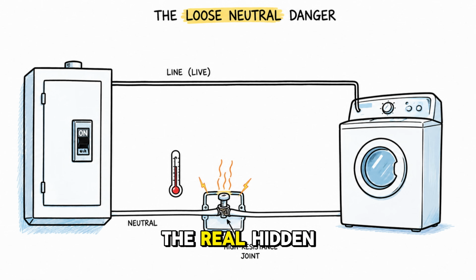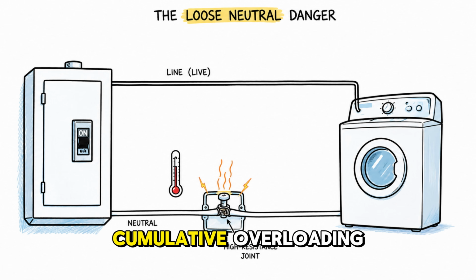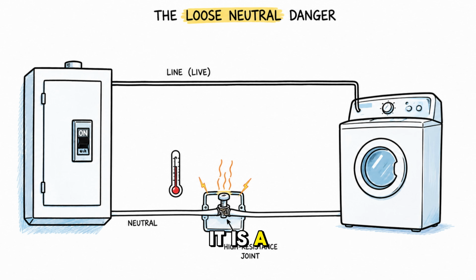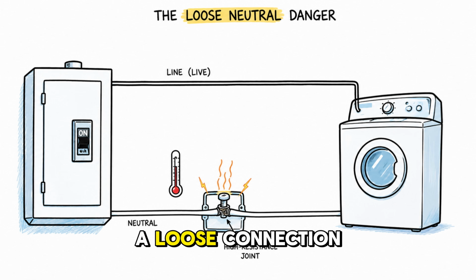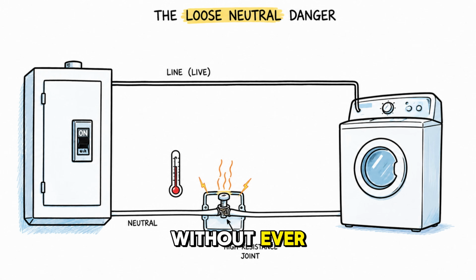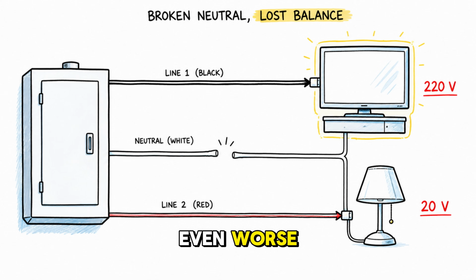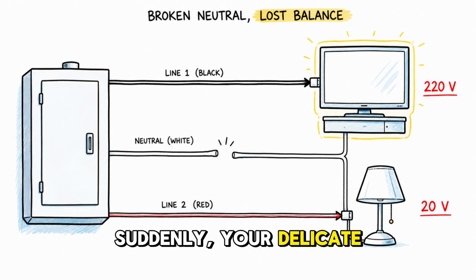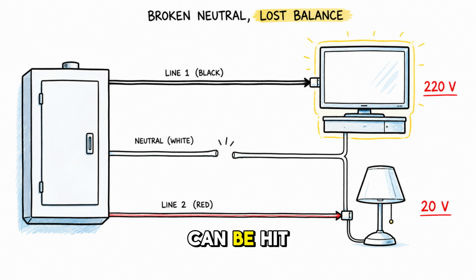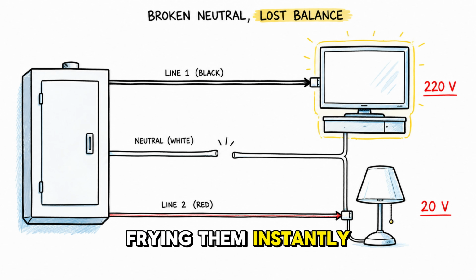Because of this, the real hidden danger of the neutral wire is not cumulative overloading. It is a loose or broken connection. Because a neutral wire doesn't have its own circuit breaker protecting it, a loose connection will cause it to arc and overheat silently inside your walls without ever tripping a breaker. Even worse, if a shared neutral wire breaks completely, it destroys the balance. Suddenly, your delicate 120-volt electronics can be hit with a destructive wave of up to 240 volts, frying them instantly.